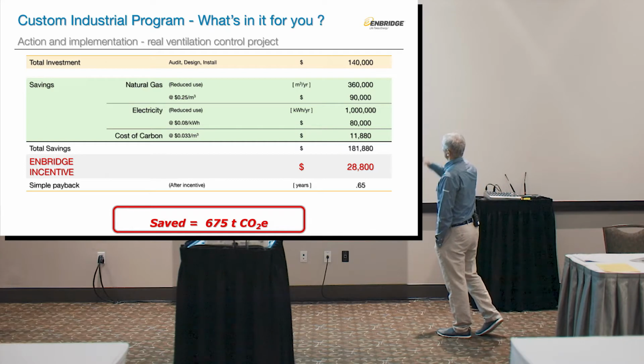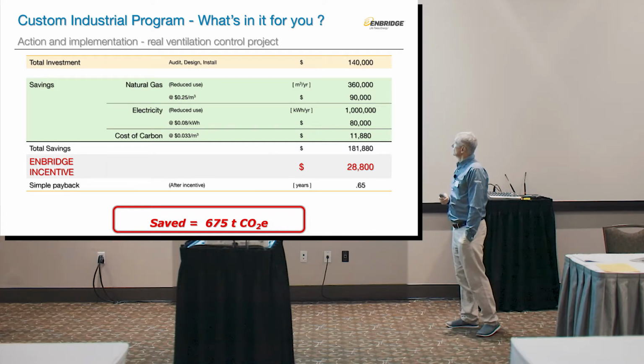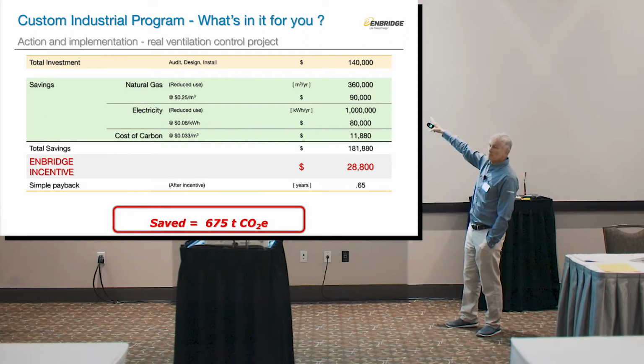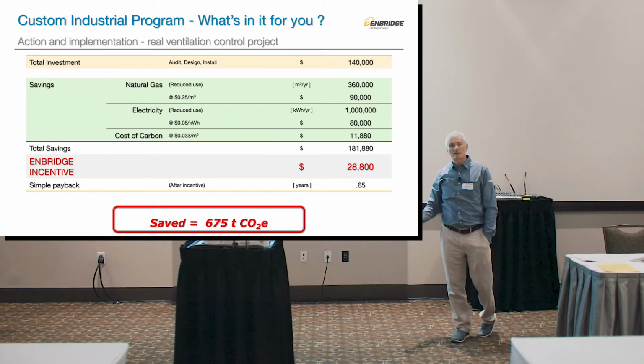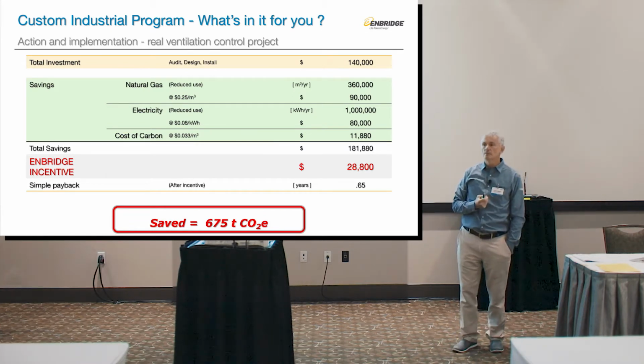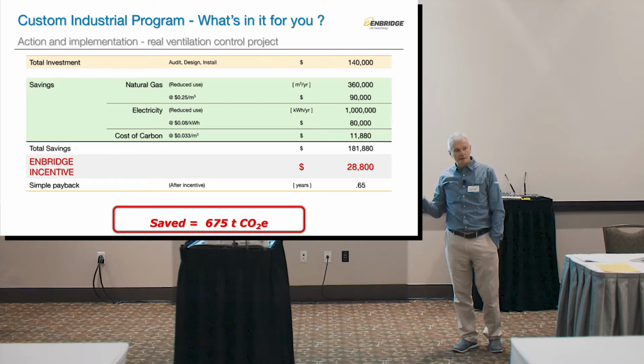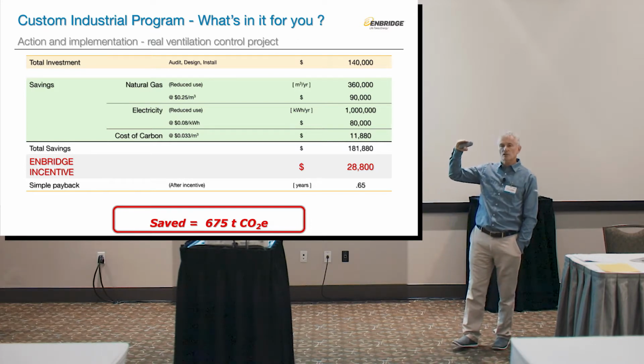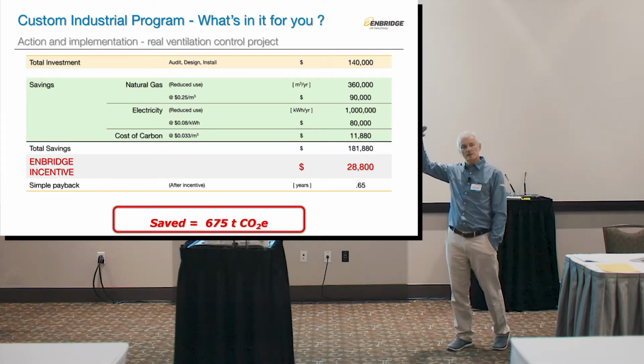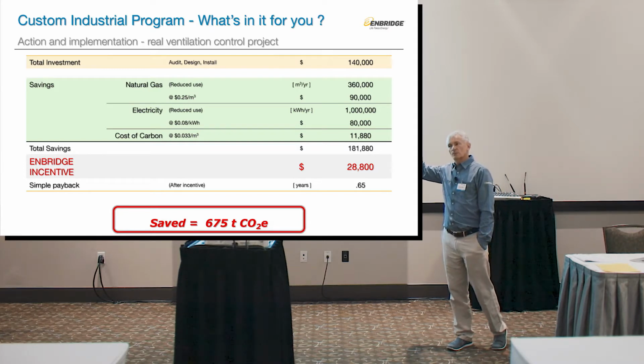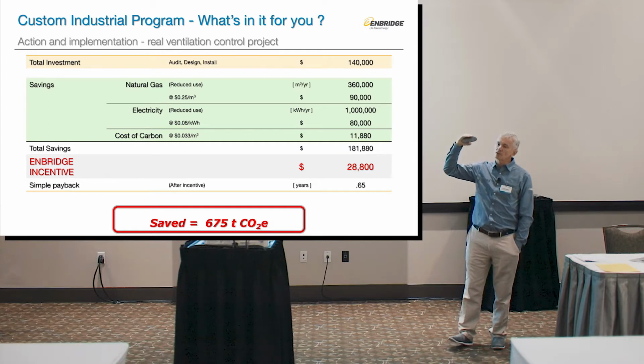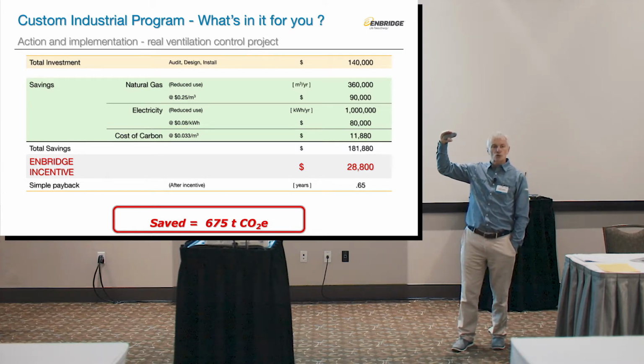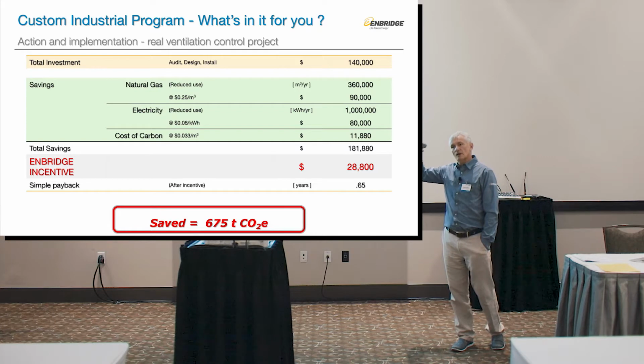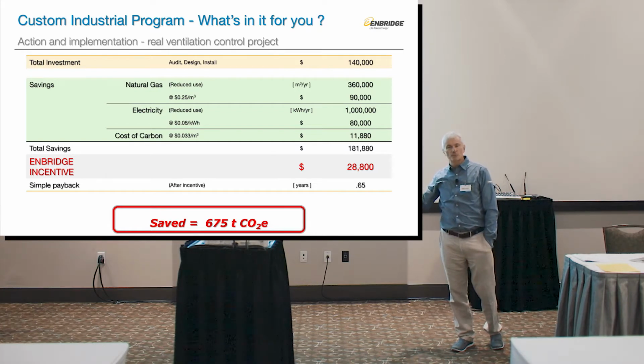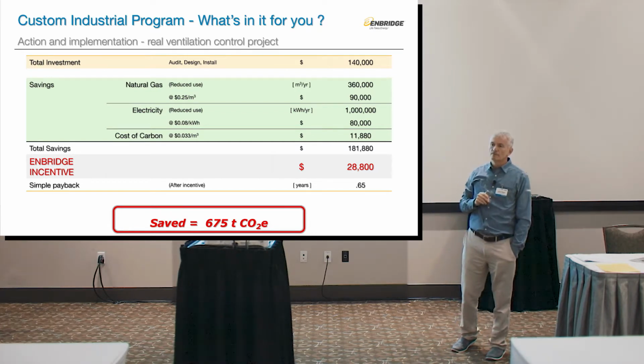They reduced natural gas by 360,000 cubic meters. They reduced electricity by 1 million kilowatt hours per year by turning off exhaust when they don't need them. And lo and behold, nothing froze. We actually put temperature data loggers at different heights before we turned the system on to make sure that over the weekend we turned off the makeup air units and we monitored the temperatures close to the pipes, near the ceiling, halfway down, at the bottom, to know that nothing's going to freeze.